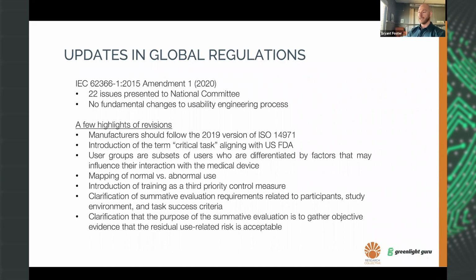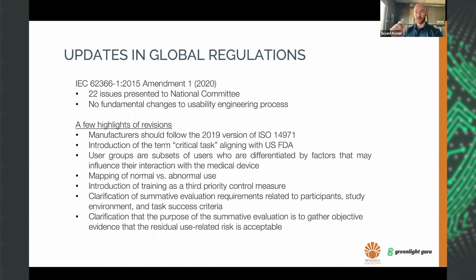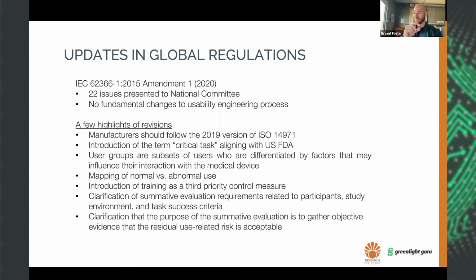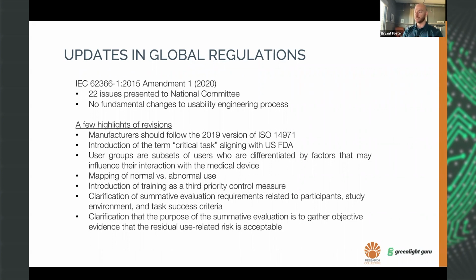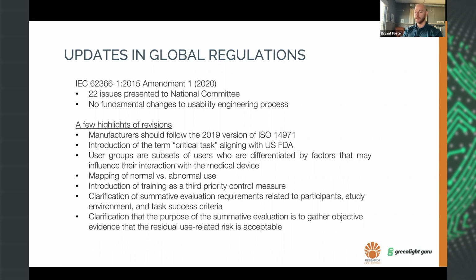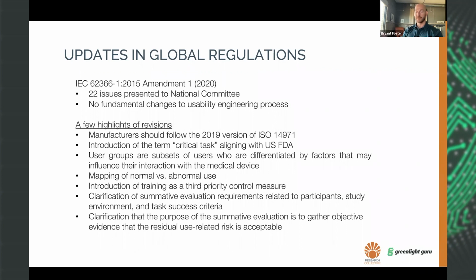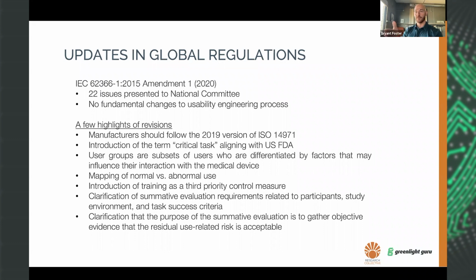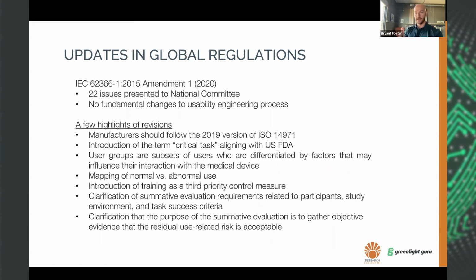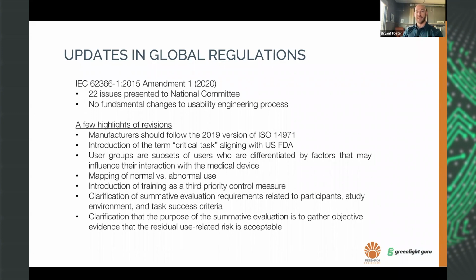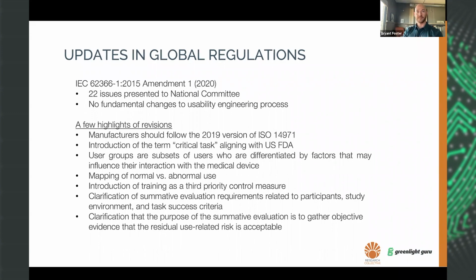And so with the added requirement for defining what is correct use for each task or each scenario, it means that success or failure of the summative evaluation is directly measured by what is observed in the summative study. So if you get failures, that could be a failure of the study or those tasks. That is cleared up by this.